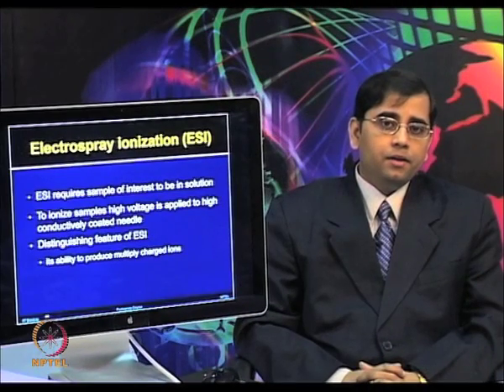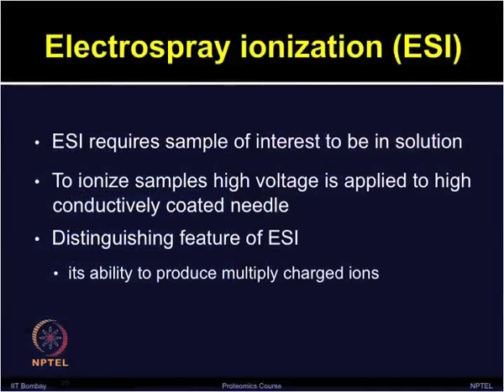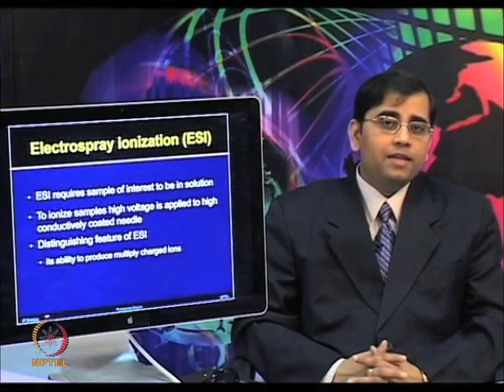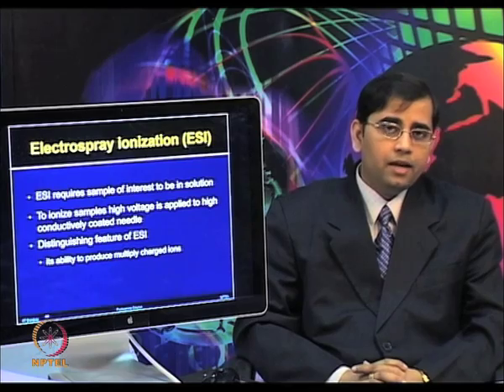ESI requires the sample of interest to be in solution. To ionize the samples, a high voltage is applied to a highly conductively coated needle, resulting in the sample becoming charged either positively or negatively. Positive ions are primarily used for the analysis of proteins. The distinguishing feature of electrospray ionization is its ability to produce multiply charged ions; the number of charges accepted by a molecule depends on its basicity and size.